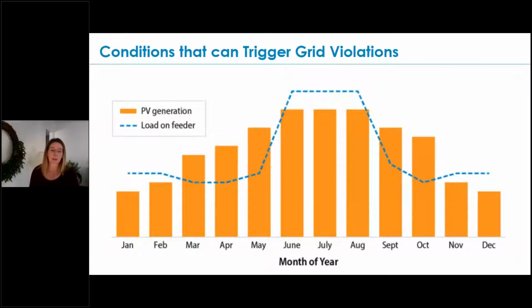A couple of the circumstances where we're seeing an increasing number of solar systems causing violations on feeders: during months of the year when PV generation is quite high, but load on the feeder is low. In this simplistic graphic, you can tell that PV generation is higher in the shoulder months, spring and fall, but load during those months is quite low because there's maybe not as much air conditioning or heating load during those months.